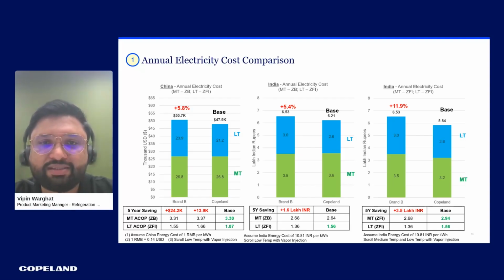The two bars on the left hand side are the annual energy cost for a combination of scroll versus semi-hermetic, medium temp and low temp. As we see here for China conditions, the savings were about 5.8%. If you look at the middle, the India conditions, with a combination of ZB and ZFI, that is medium temp and low temp, against semi-hermetic, a similar amount of savings can be seen. And for India, the 5-year savings were close to 1.6 to 2 lakh rupees, which is 5 to 6% over the base.